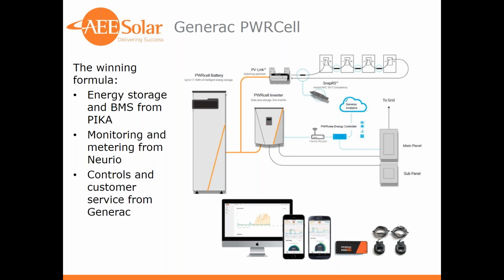I'm an old inverter guy at heart, so we'll start there. It starts with the Power Cell inverter, which is a hybrid inverter capable of simultaneously inverting to AC while charging batteries. To operate in today's environment with module level rapid shutdown, they have a two-part solution. Part one is a PV Link, a substring optimizer that will optimize output for strings of up to 4 modules. To be code compliant with 2017, they have SnapRS, which is a really clever inline shutdown device. It takes signals from the PV Link, which takes grid sense signals from the Power Cell inverter, and because the PV Link is optimizing the substring voltages, it is able to communicate to SnapRS to say shut down or keep operating.